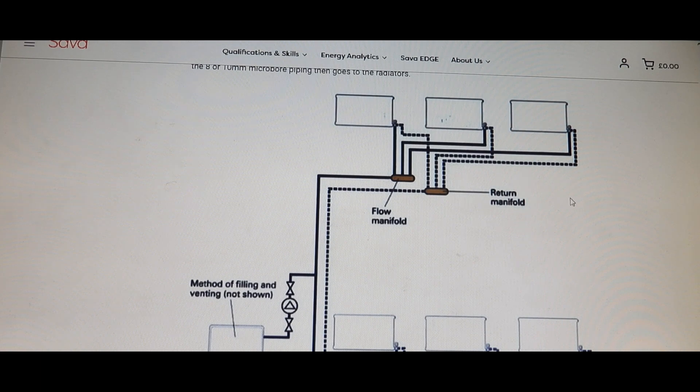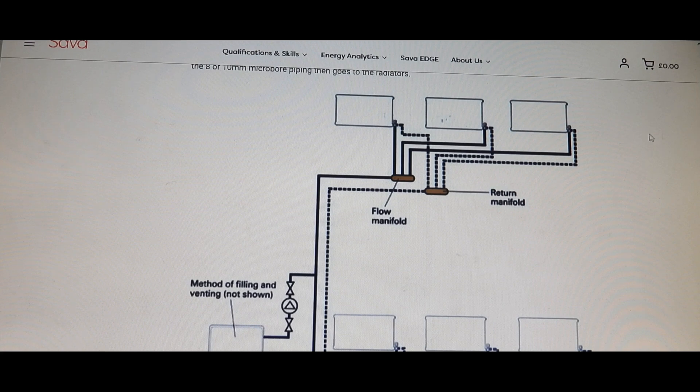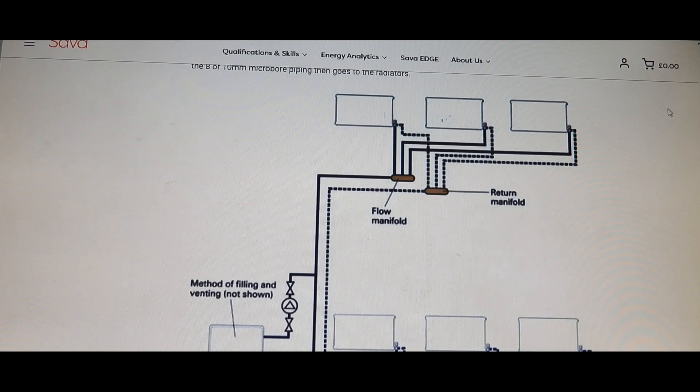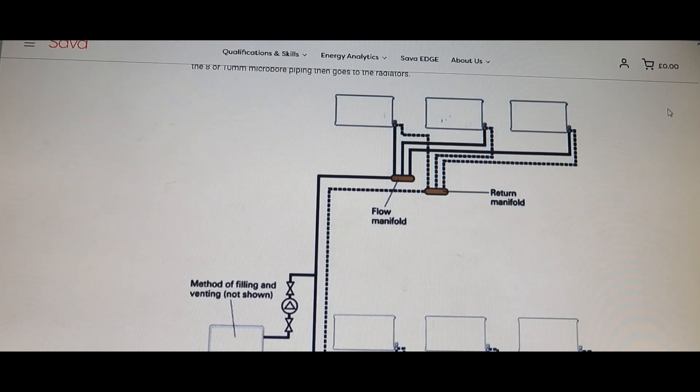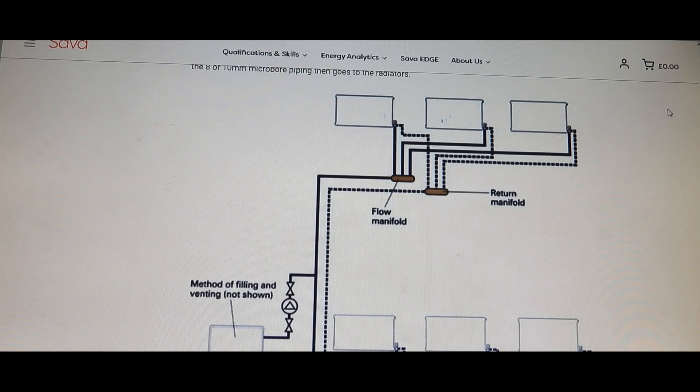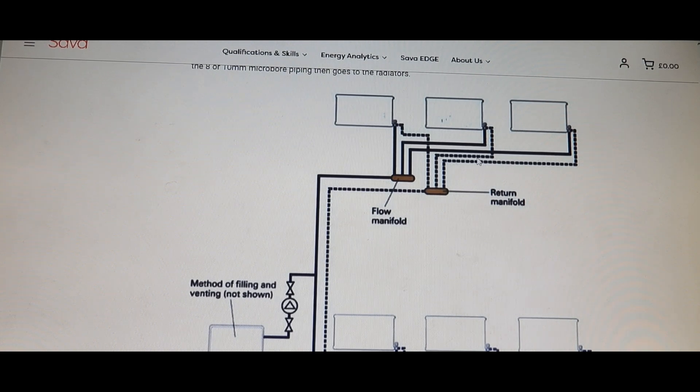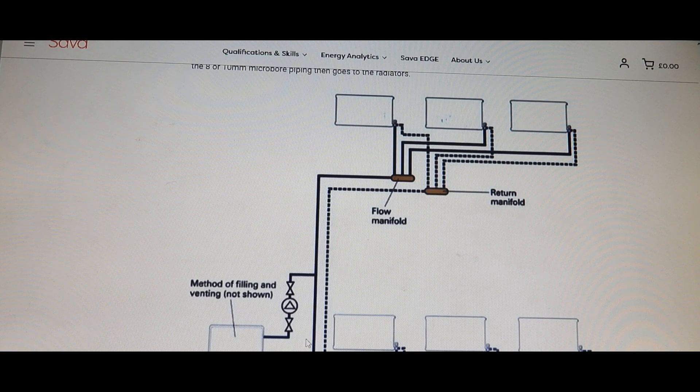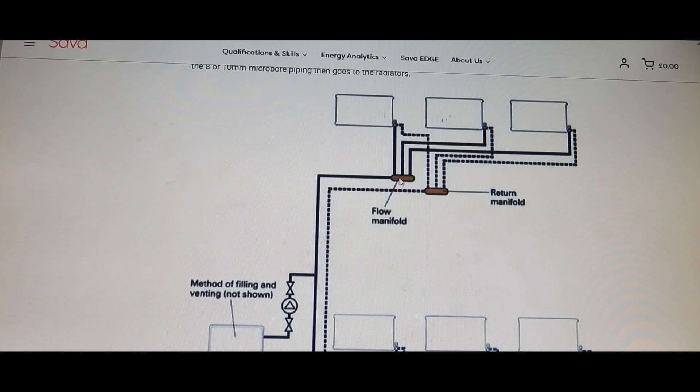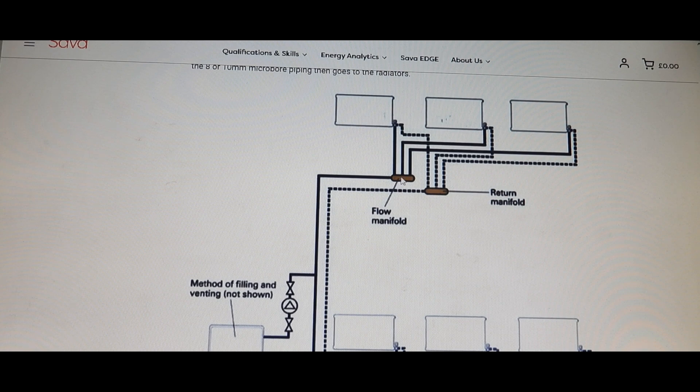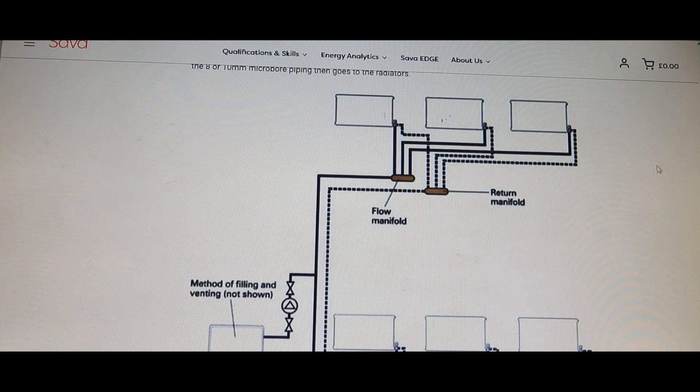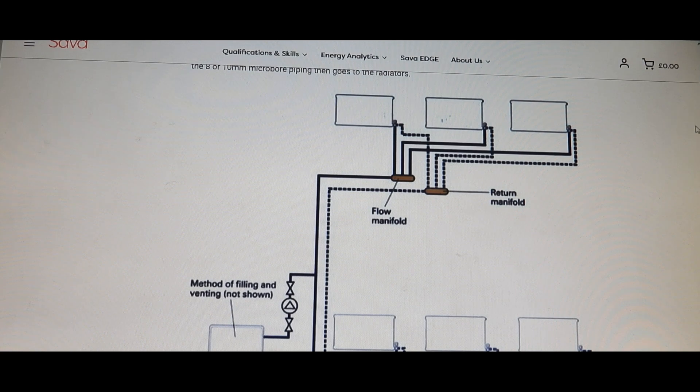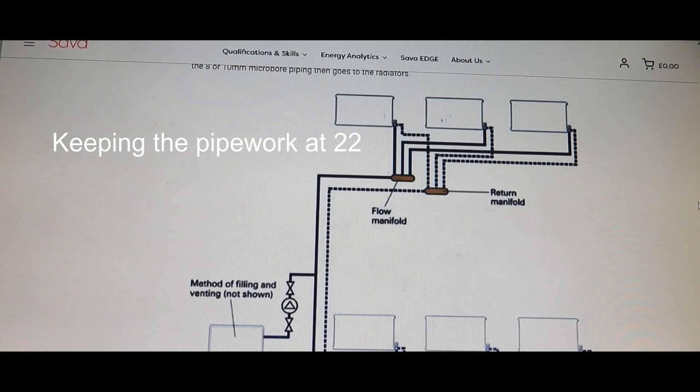If you start running it over long lengths it will never return and put extreme pressure on the pump and the system to work. So it's no good going way off into other rooms that are a long way away from these manifolds. You then have to think about, I know this is 22mm pipe up to these manifolds, but you'd have to think about actually undoing and moving the manifolds along so it's more central to where your other rads are going.